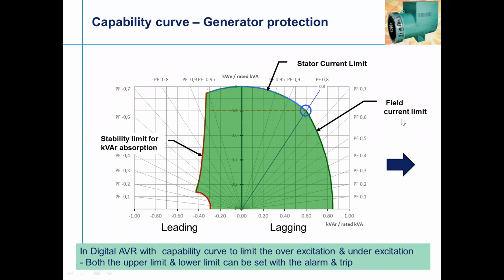So why I'm saying the field current: this is a part of our excitation system. Again, it decides how much I excite, how much load the stator can take, and how much reactive power I can absorb. If you keep more than that, I'm gone. That's how these limits have been set. Earlier the protections were outside. Today they have been brought inside the generator. That's why I appreciate this digital technology. So there is a rating point of what you can do.